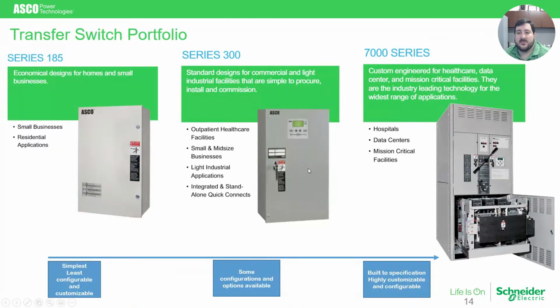ASCO has several types of transfer switch platforms, ranging from our Series 185 platform, which is our simplest and least configurable product, really meant for residential and small scale applications. In the middle range, we have our Series 300, meant for more commercial applications that offer some more degrees of configuration within the controller, with time delays and pickup and dropout settings for voltage trip levels, and has some options. But today's presentation will mostly be focused on the 7000 series transfer switch, which is really geared towards critical applications such as hospitals and data centers.